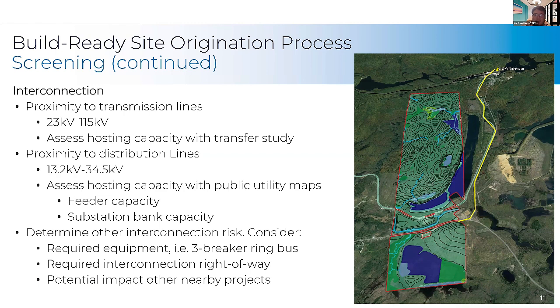An assessment of the distribution line hosting capacity can be made by entering these utility-specific hosting capacity maps. These resources show the amount of energy projects connected or queued on a given distribution line and its host substation bank. By looking at the amount queued and connected against the limits of the line and the thermal limits of the substation bank, one can determine the hosting capacity of the substation and whether there's enough to fit a new project.